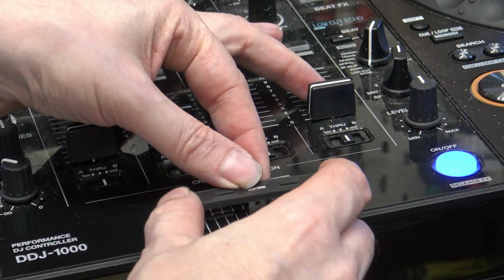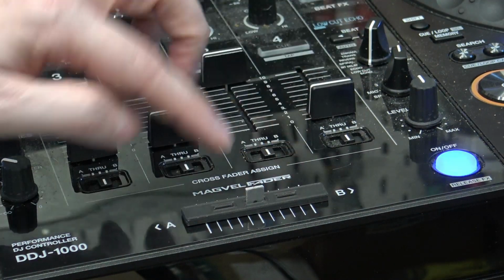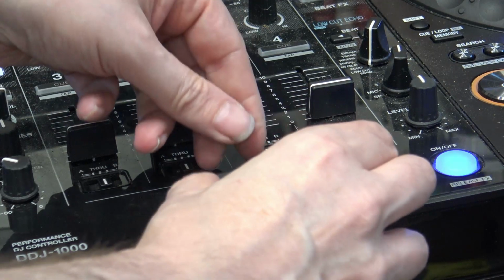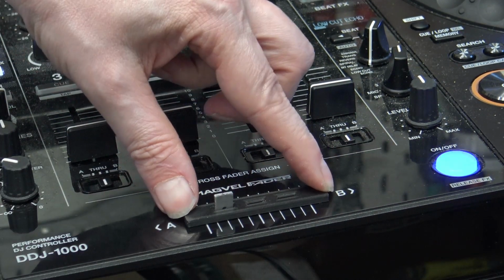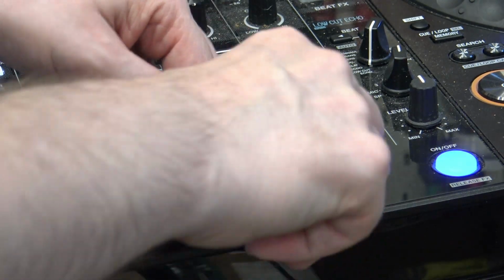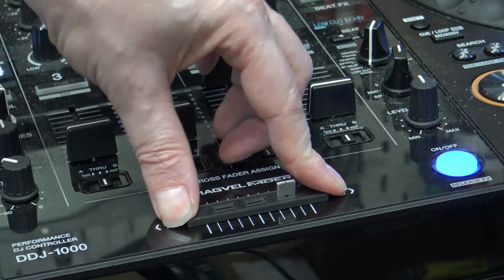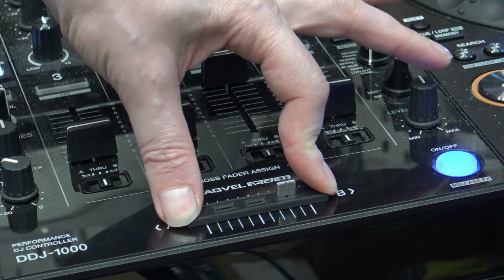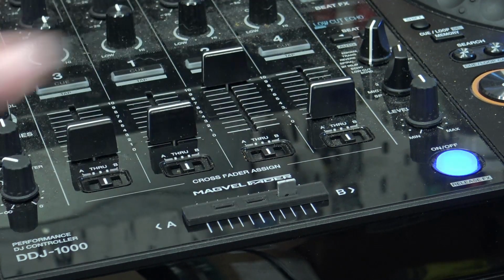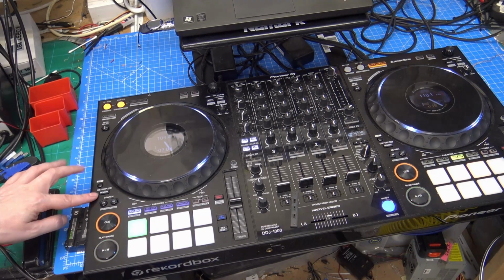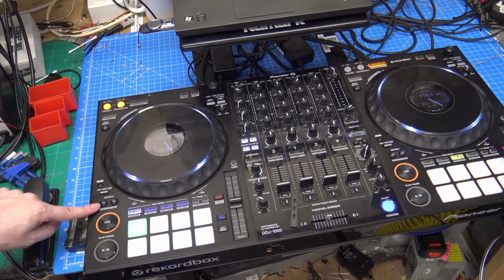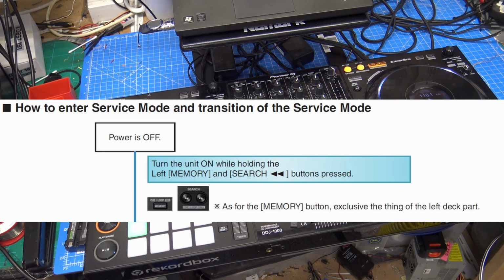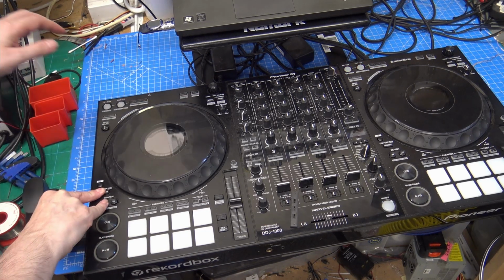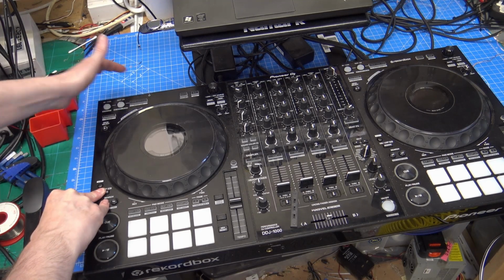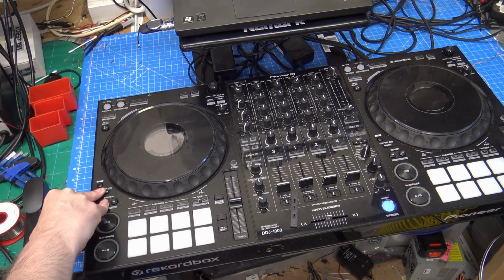So it fits in, it's very snug, and then there are little bits on the bottom that lock it in place. Then we can put it to that position and it lines up with that 3rd tick, and then the other side. And because it has those little notches on the bottom, it locks it in place, so it should be in the right position for calibration. So first step is to enter service mode, which on the left deck is memory and search backwards while we're turning it on. So memory, backwards search, turn it on. So it doesn't do the normal test when you start it up.